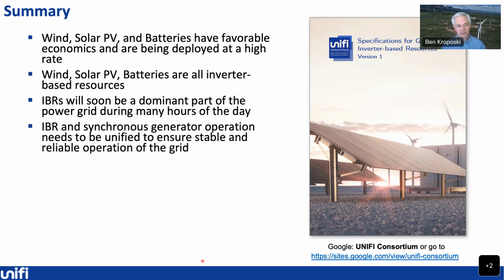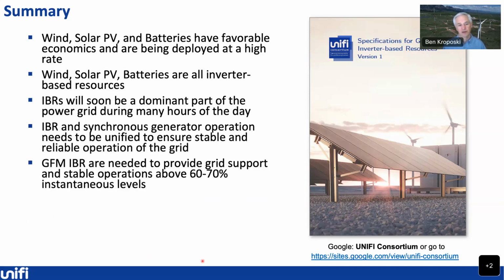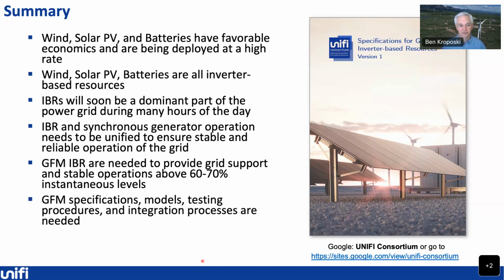And we need to ensure that these inverter-based resources and synchronous generators work together in a unified approach to ensure stable and reliable grid operation. As I showed you earlier, grid forming inverters are needed to provide grid support and stable operation above 60 to 70% instantaneous levels, which translates to maybe 25 to 30% on an annual basis. And there are lots of power grids in the United States today that are starting to reach those levels.